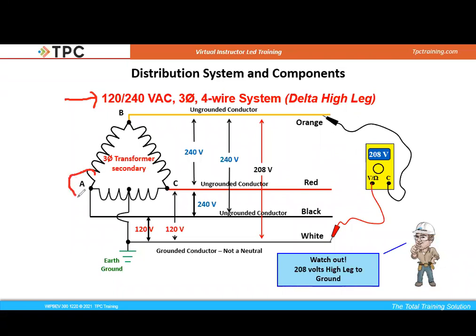On phase A to my neutral, no problem. That would be 120 volts. That would be no issue whatsoever. Phase C to my neutral, again, no problem, 120 volts. But here's the one that's a little bit off. It would be phase B to my neutral, and that would be at 208 volts.